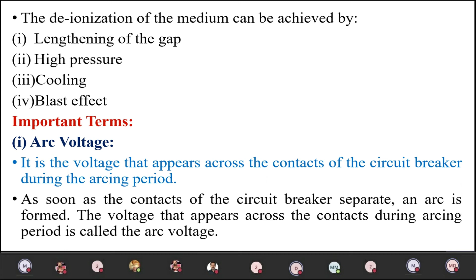The value of the arc voltage is low, except for the period when the fault current is at or near zero current point. At current zero, the arc voltage rises rapidly to peak value, and this peak voltage tends to maintain the current flow in the form of arc. So this is the concept of arc voltage. Second important term is restriking voltage.